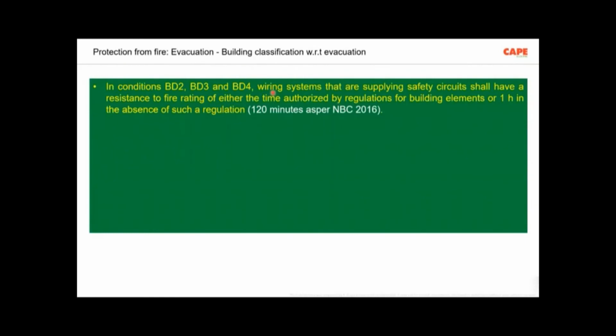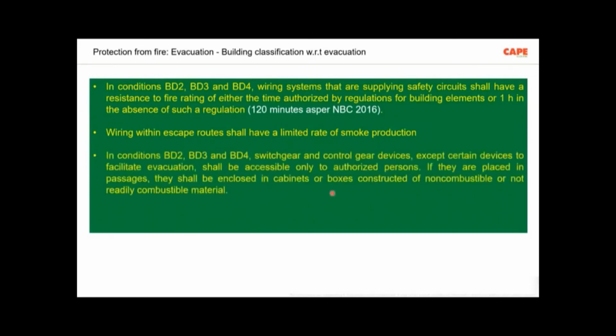It is not only the wire. Please understand, there is a new IS code for fire resistant wires, but using the wire alone will not ensure safety. The entire electrical wiring, the fixing materials, the distribution board, the entire system should have a functional guarantee of 120 minutes. I would say 120 minutes is a little bit higher. Even 60 minutes or 1 hour itself is enough. But anyway, it is the subject of the National Building Code.